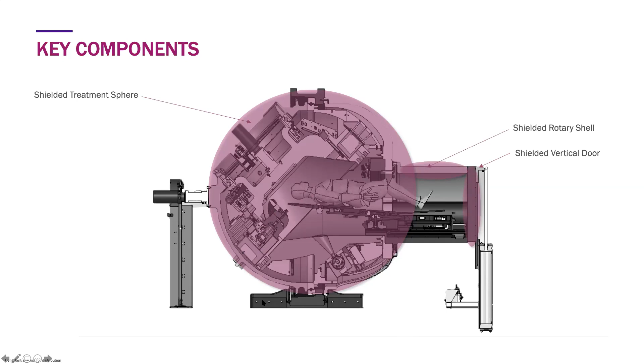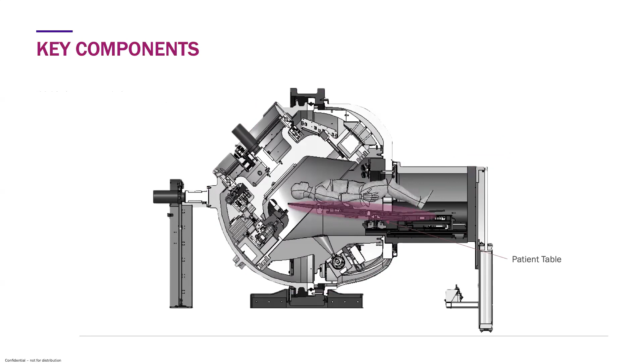Those two rotational degrees are mated with a table that is 3 degrees of freedom, and then a collimation system with a fourth, yet another degree of freedom, giving us an aggregate of 6 degrees of freedom. So we like to refer to this as a radiosurgical robot. Radiosurgical robot, it's really optimized for brain and head and neck radiosurgery. The KV imaging system, here's a KV source. There's a flat panel detector, rotates around the patient, and by using X-ray image-to-image correlation and the patient's original CT anatomy, we are able to know with sub-millimeter precision, with sub-millimeter accuracy, where the tumor is located in space, and then to move the table to put that tumor at isocenter.